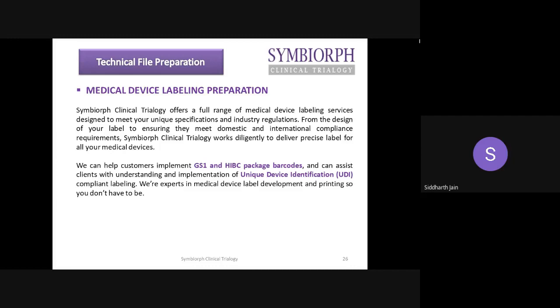UDI is further divided into UDI-DI and UDI-PI. UDI-DI means device identification number, and UDI-PI means production identification number. So UDI-DI plus UDI-PI is equal to UDI. You have to define your devices under MDR, and then approach GS1 to issue you this UDI number, and then you can have all this barcoding or UDI number on your labels. So this is currently the new requirement released by the European Commission to fulfill. Next slide, please.